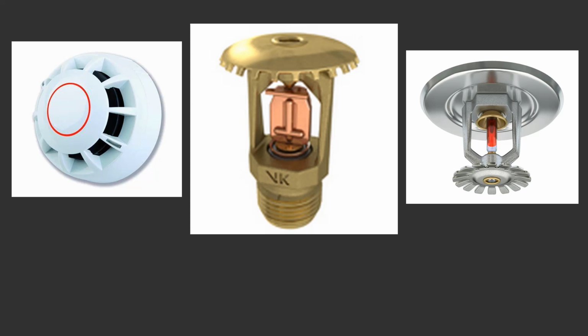Again, I don't think I've ever seen one of those, or maybe once. I'm more familiar with the one on the far right, which is our frangible bulb. Again, we're using 180 as an example. For the record, the colored liquid in there changes color depending on the temperature. Someone might know off the top of their head, or you can look up what a red frangible bulb means, and I'll say like 160 degrees or whatever it may be. The little vial acts the same way the link does. When it gets to 180, in our example, the liquid expands, it breaks the little vial, the spring plunger opens, and water comes out of the sprinkler.